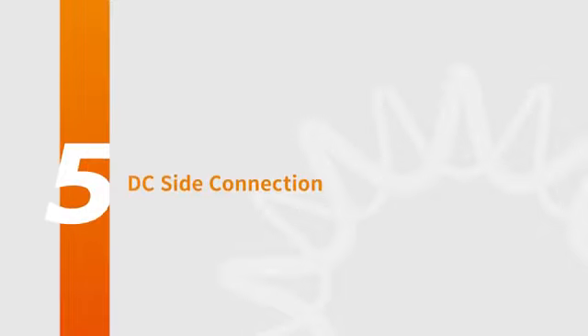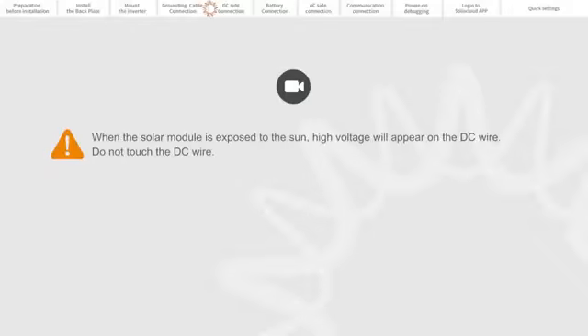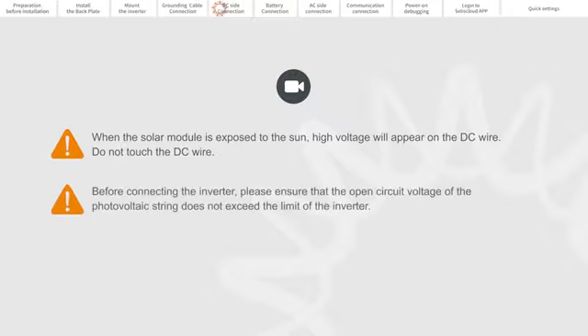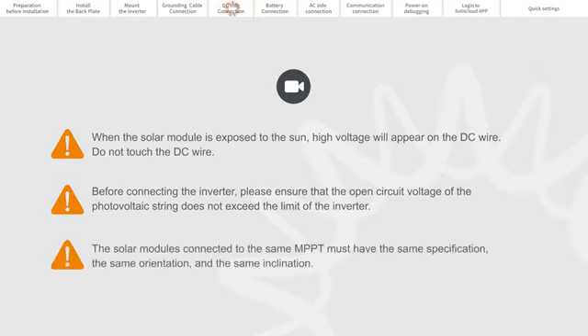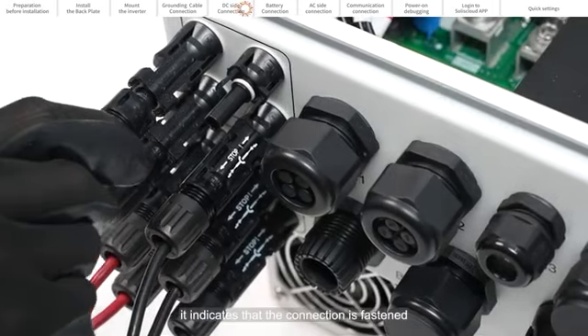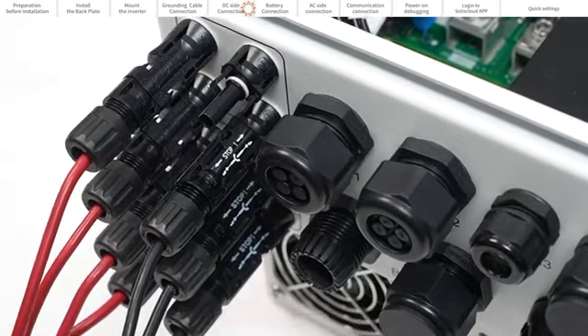Part 5. DC side connection. When the solar module is exposed to the sun, high voltage will appear on the DC wire. Do not touch the DC wire. Before connecting the inverter, please ensure that the open circuit voltage of the photovoltaic string does not exceed the limit of the inverter. The solar modules connected to the same MPPT must have the same specification, the same orientation, and the same inclination. When you hear a click sound, it indicates that the connection is fastened.